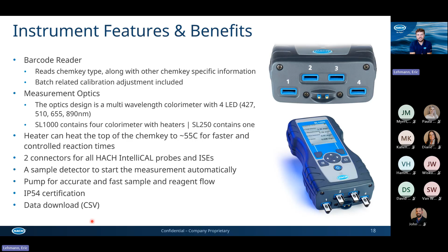So let's talk about how we actually take measurements with this. First of all, you have the chem key itself. You open the chem key, insert the chem key into the instrument, place it in the sample cup, and then you wait for the results. So let's go ahead and do that. I have my instrument right here in front of me. Just going to power it on. It's kind of hard to see with the background, but it's telling me to insert a chem key or connect a probe. So let's go ahead and do that.